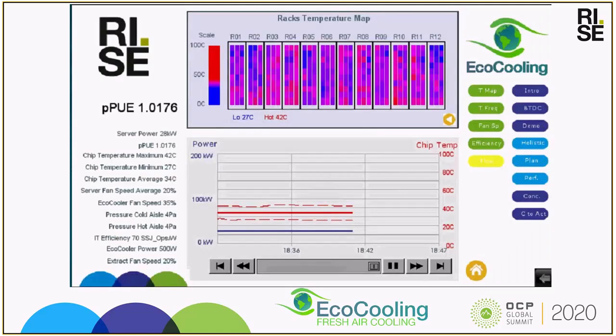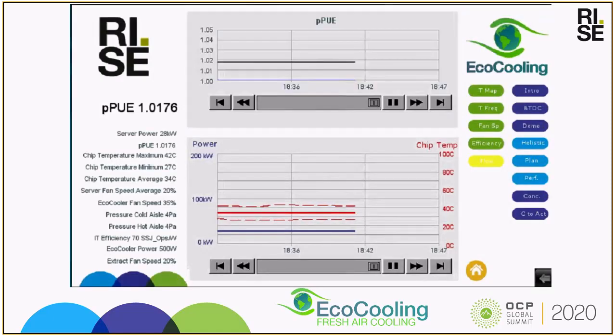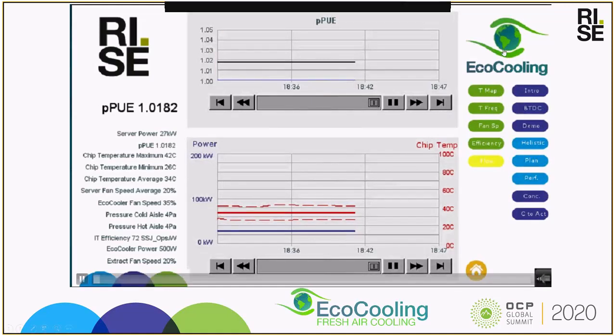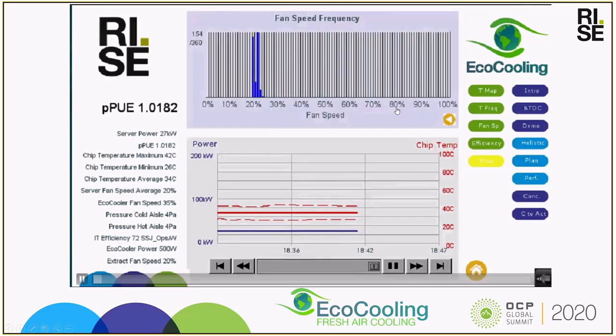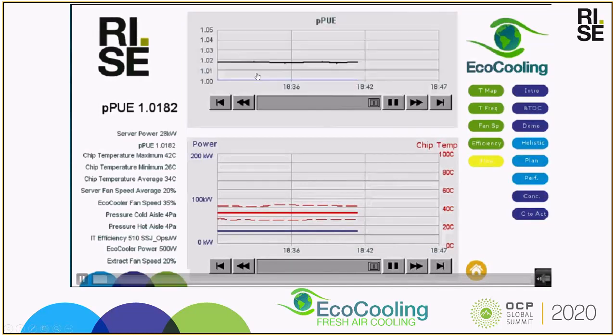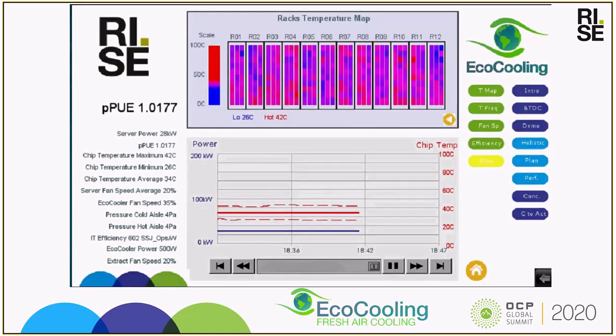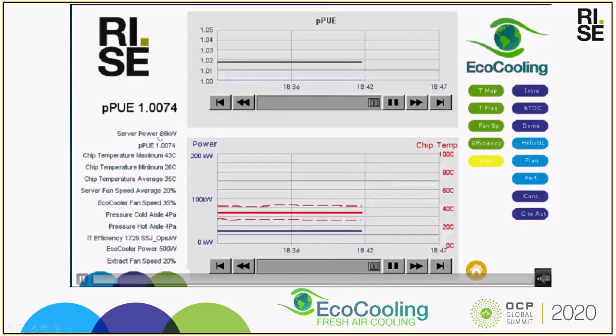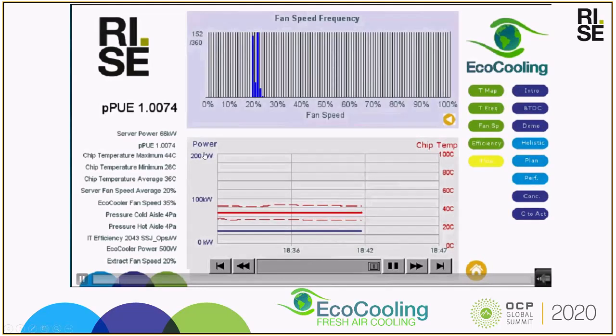Here you can see the interface to the cooling control system that was produced by EcoCooling based on open source software. What you see here is a histogram of the server fan speeds. This is information provided to this control system over Modbus. We're providing the microprocessor temperatures, so we can produce a heat map like this, and see what the lowest temperature is and the hottest temperature is. At the moment, the servers are idle, they're doing no workload. Well, just at that point it was, and now we've started to increase the workload.